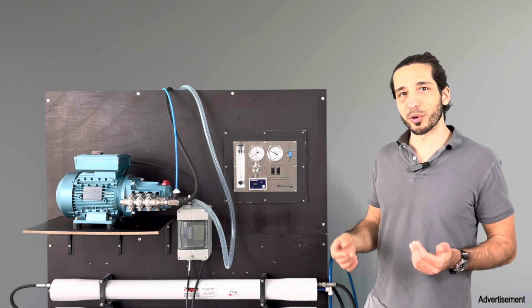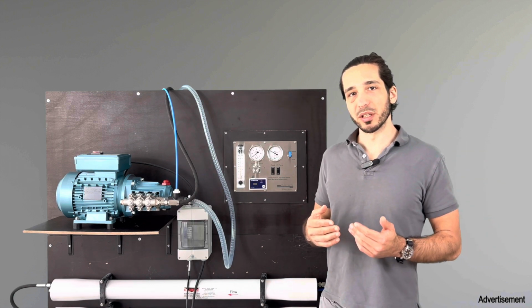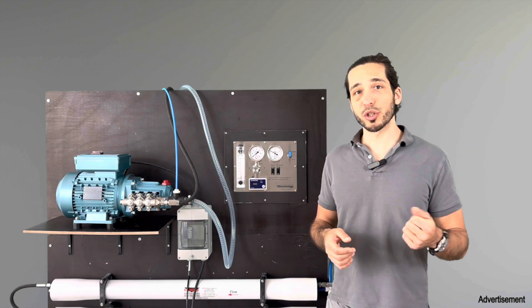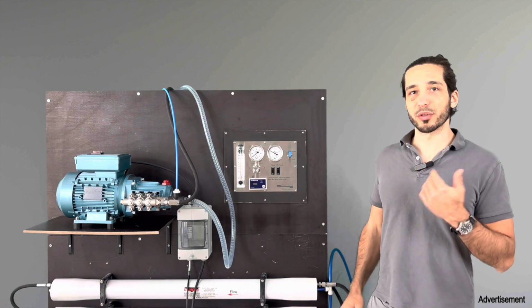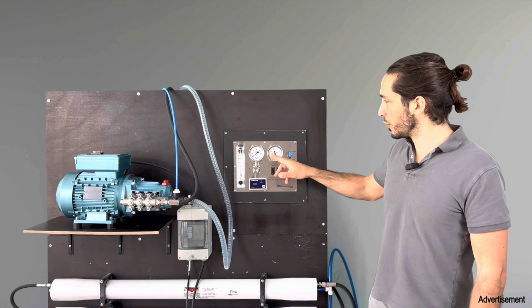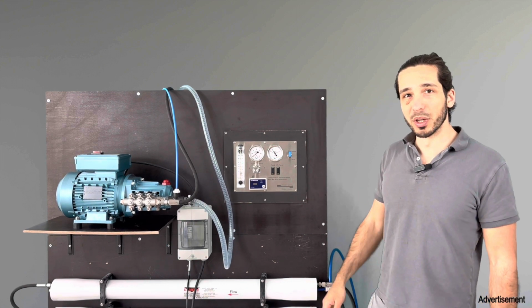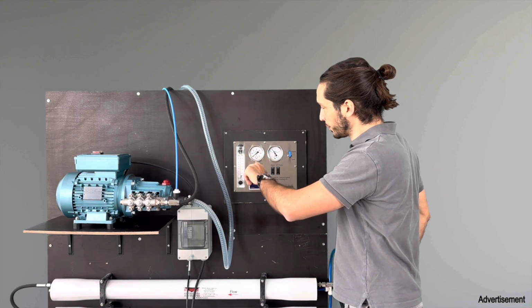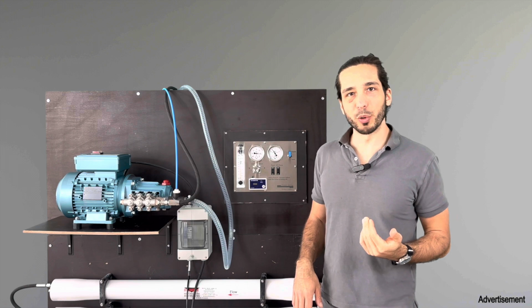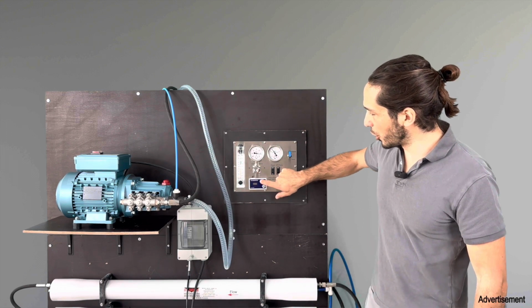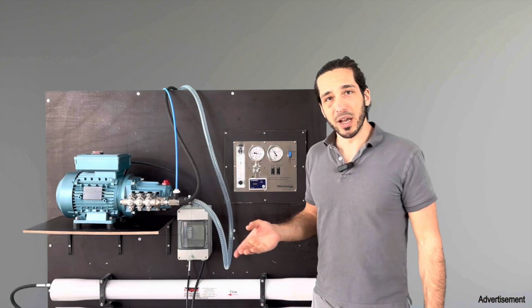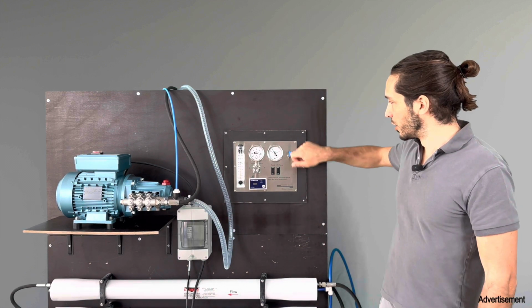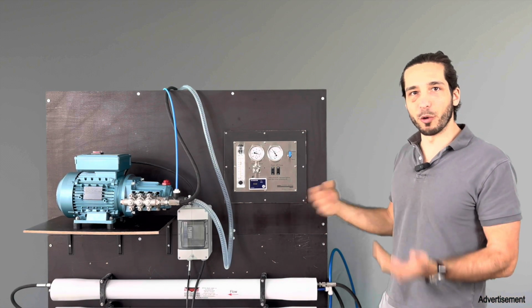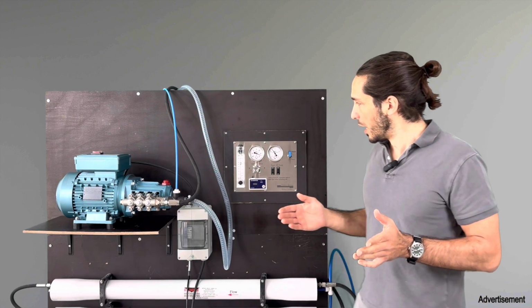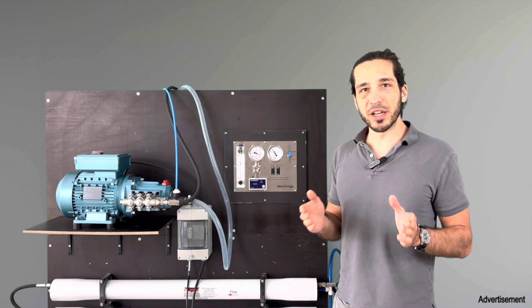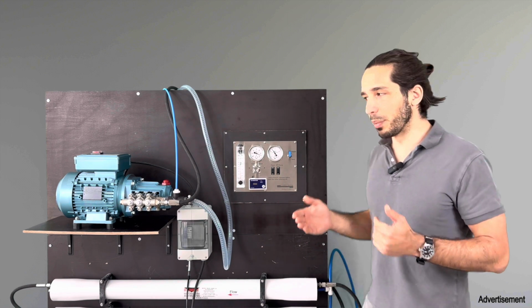The normal production run differs from the commissioning run only in that you don't wait for such a long time before you start increasing the pressure or before you divert the product water into your tanks. So in a normal production run, you just switch on the feed pump. You see the pressure increasing here. You switch on the high pressure pump, and then you can already start increasing the pressure. Once you reach the typical operational pressure, you see the product water flowing. You switch on the TDS monitor and can check the TDS. As soon as the TDS drops below 500, you can divert the product water into your tanks, and the water production is going. As soon as you decide that you produced enough water, you stop the system by releasing the pressure.